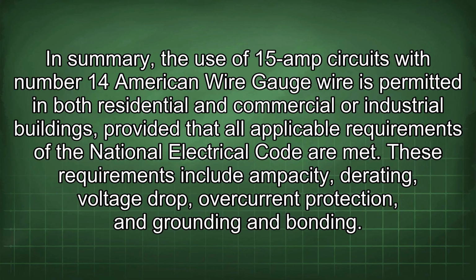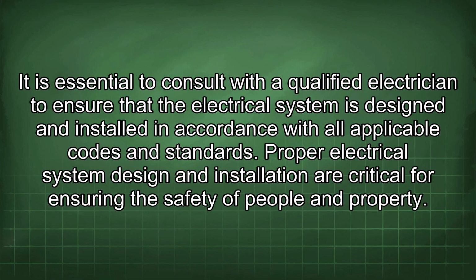In summary, the use of 15-amp circuits with number 14 American wire gauge wire is permitted in both residential and commercial or industrial buildings, provided that all applicable requirements of the National Electrical Code are met. These requirements include ampacity derating, voltage drop, overcurrent protection, and grounding and bonding. It is essential to consult with a qualified electrician to ensure that the electrical system is designed and installed in accordance with all applicable codes and standards. Proper electrical system design and installation are critical for ensuring the safety of people and property.